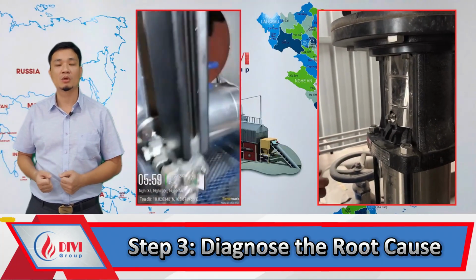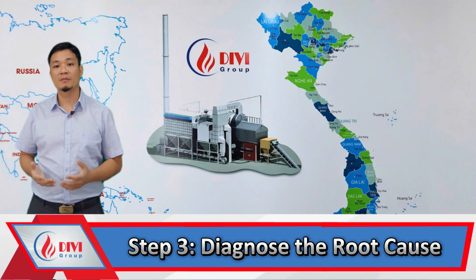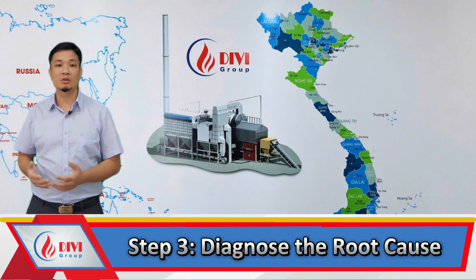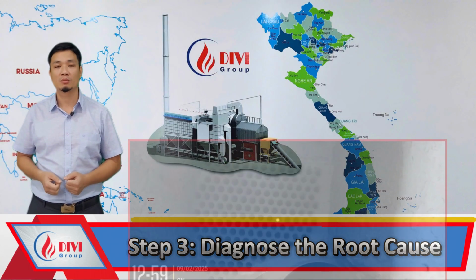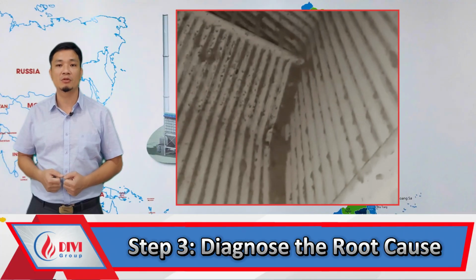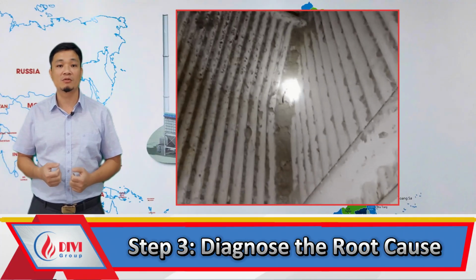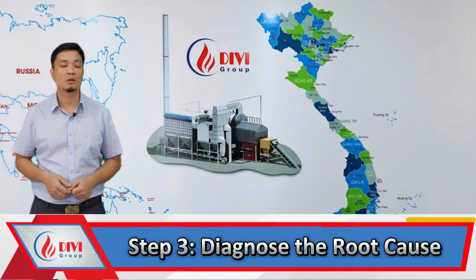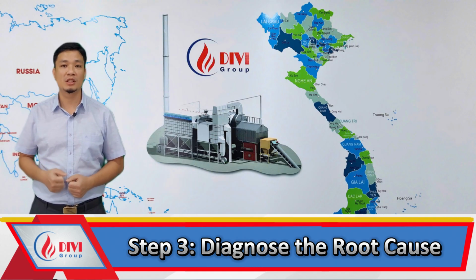Wait for the boiler to cool completely before entering. Once pressure has dropped to zero, enter the boiler and check all pressure-bearing parts to see if there is any steam leakage or visible water seepage. Inspect the steam-generating tubes carefully for signs of cracks, deformation, or other damage caused by overheating.